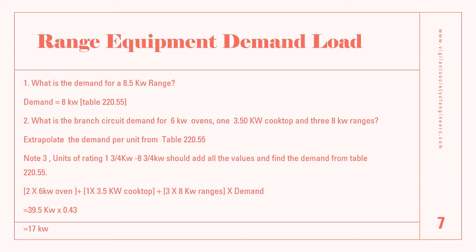Next, we look at range minimum demand. Say we have a range of 8.5 kilowatt and need to find the demand. We simply go to Table 220.55 and extract the value. This value falls under column C — the demand for a range less than 12 kilowatt. For one unit, the demand from the table is 8 kilowatt.